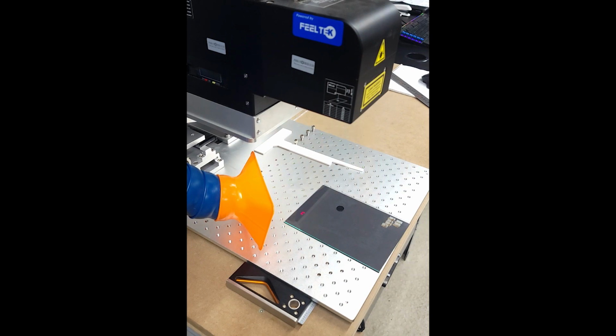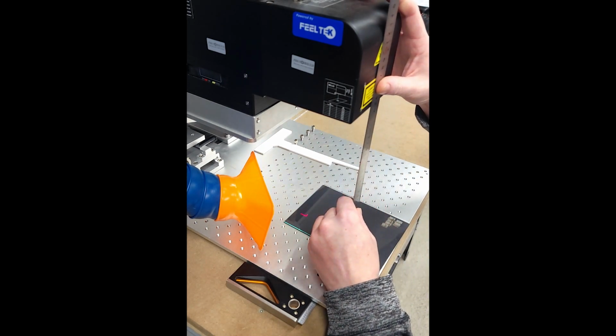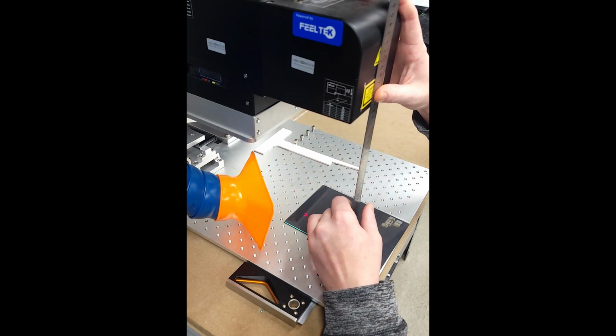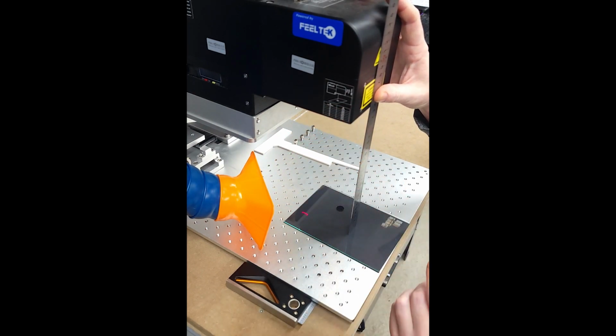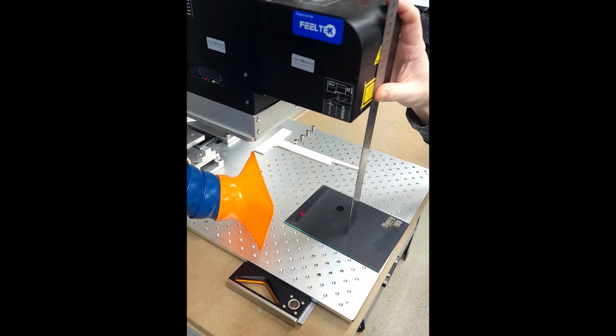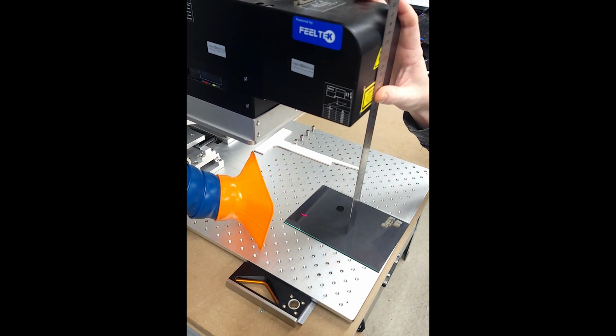Now what we want to do here is we want to start at our first focus value, which you'll see on the side of your head. We start at 234, so let's get down there. And again, be very particular about how accurate your measurements are here, and through every step of this process. This is the key. If you're going to be off on these measurements, then your calibration settings are going to be off as well.